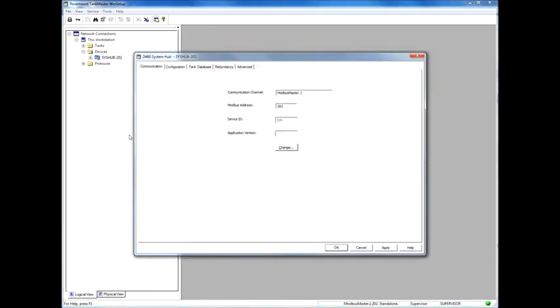Here we have the Rosemount TankMaster, which we are going to use to configure the redundancy mode. There is one 2460 available, we right click, we choose Properties. There we have a Redundancy tab and we go to that one.